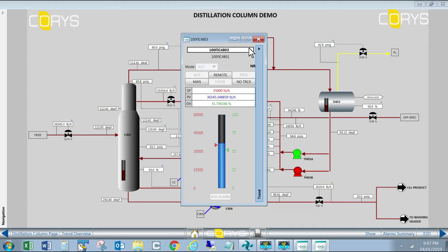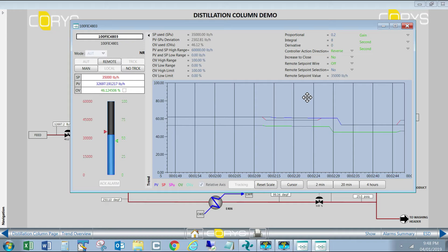So I'll go to the instructor, make sure that I'm running the simulation, and now the operator basically can open like a PID faceplate for this flow controller, change the set point, maybe decrease the flow to 35,000. So you can see the valve is closing. You can monitor it on the trend. You can put the controller in manual and reduce the valve output to say 45%. So you can see green is the controller output, red is the set point, and blue is the PV. So it went down. You can put it back in auto and give the normal set point of 35,000 and let the controller take the process back.